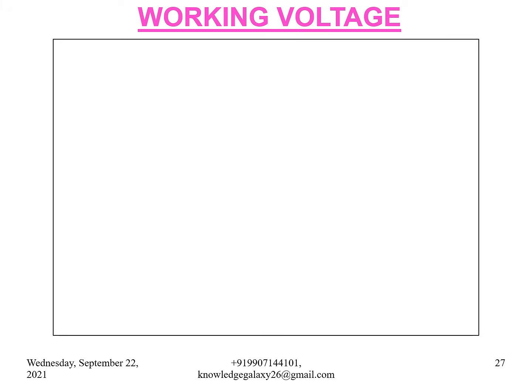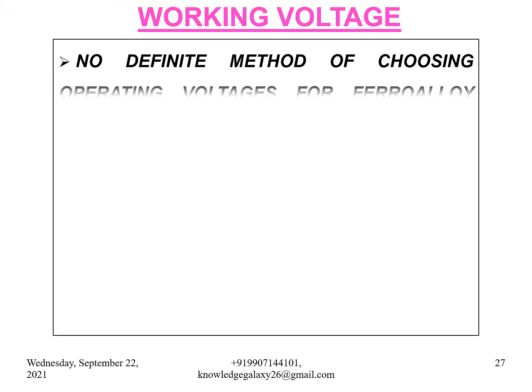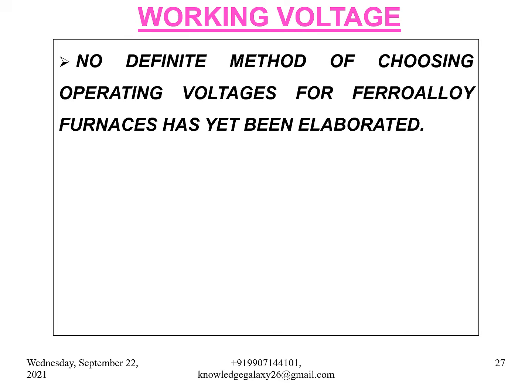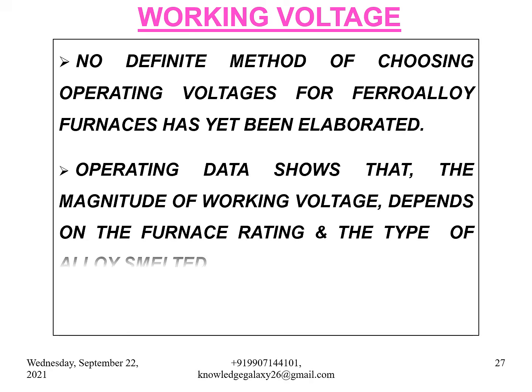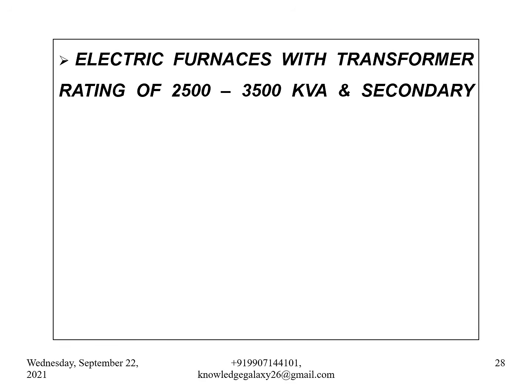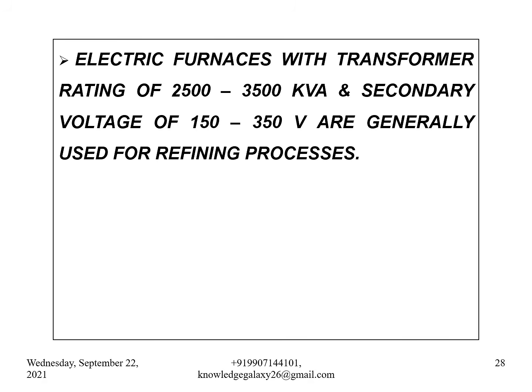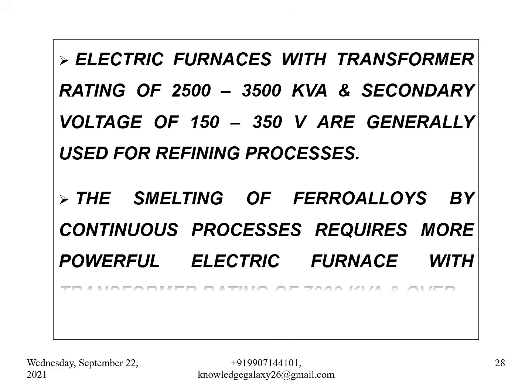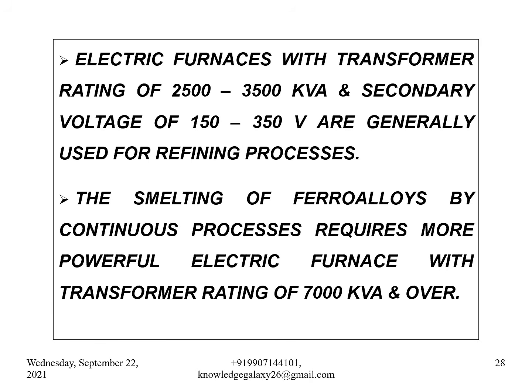Now let us discuss working voltage. No definite method of choosing operating voltages for ferroalloy furnaces has yet been elaborated. Operating data shows that the magnitude of working voltage depends on the furnace rating and the type of alloy smelted. Electric furnaces with transformer rating of 2500 to 3500 kVA and secondary voltage of 150 to 350 volts are generally used for refining processes. The smelting of ferroalloys by continuous processes requires more powerful electric furnaces with transformer rating of 7000 kVA and over.